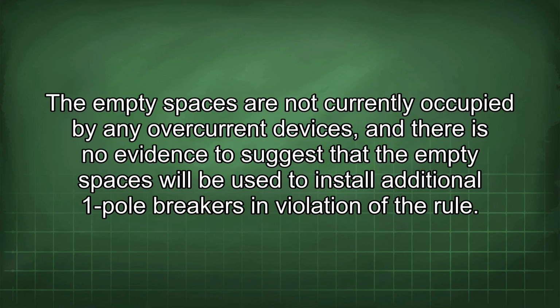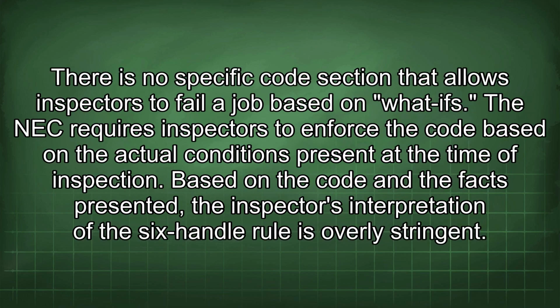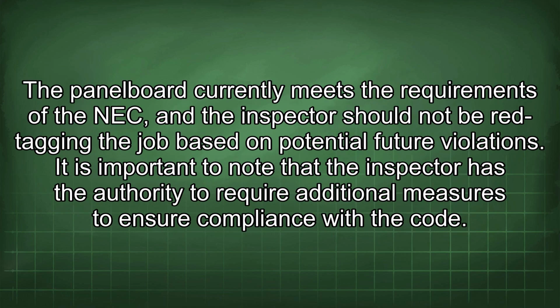The empty spaces are not currently occupied by any overcurrent devices, and there is no evidence to suggest that the empty spaces will be used to install additional one-pole breakers in violation of the rule. There is no specific code section that allows inspectors to fail a job based on what-ifs. The NEC requires inspectors to enforce the code based on the actual conditions present at the time of inspection. Based on the code and the facts presented, the inspector's interpretation of the six-handle rule is overly stringent. The panel board currently meets the requirements of the NEC, and the inspector should not be red tagging the job based on potential future violations.